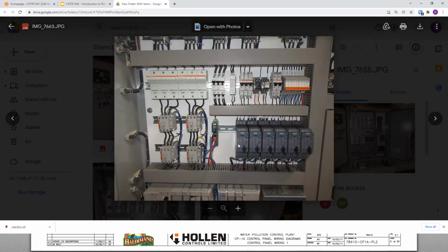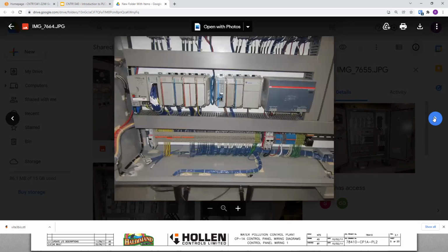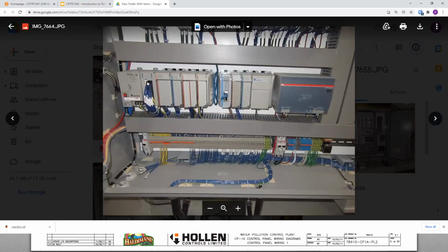And then the user's asking whether these starters have built-in circuit breakers, or are those just starters so you can start it across the line? So that will trip. If it's a short, that will trip like a circuit breaker. It'll trip at 45. And then there's also another, where that little blue button is on the top right there, Reset. That's where the overload is, so that would be the overload trip. Timers are just normal relays. One's a timer and one's a relay. Okay.